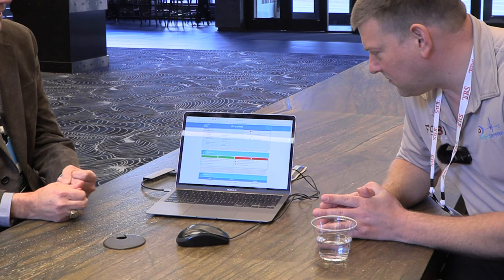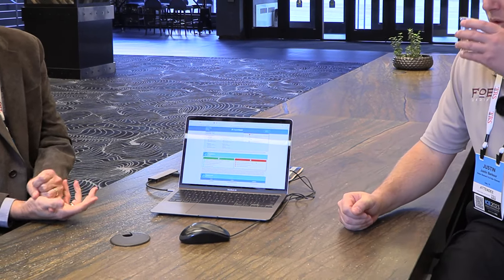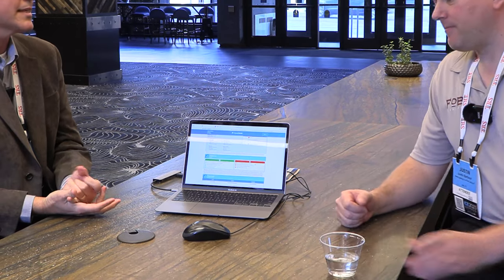In the trends section, we do things like — if a device needs calibration, we say it probably needs to be calibrated at least once a year. So if it doesn't show a calibration event in the record, it'll flag that. Same for PMs, inspection checks, yearly maintenance — things like that. A lot of this is really for the end user. If you have a buyer looking at a C-arm, this could help them decide whether they want to buy it or not. If you have two like items and everybody sells around market value, but you have more information on one versus the other, it makes the purchasing decision much, much easier.